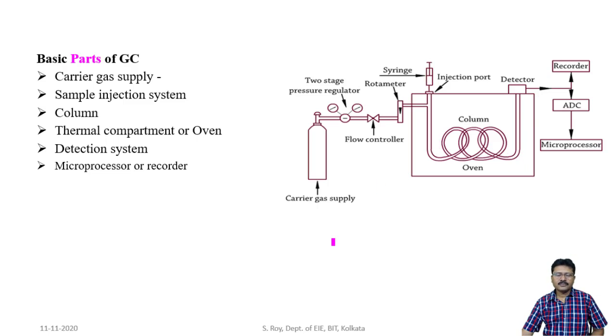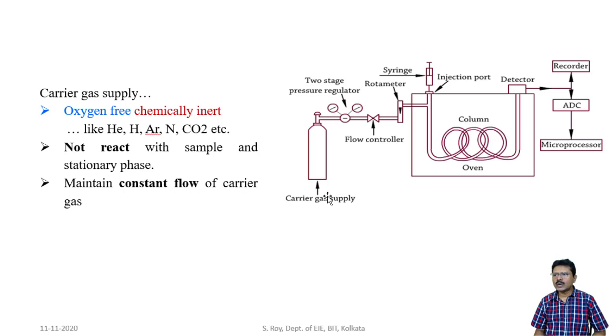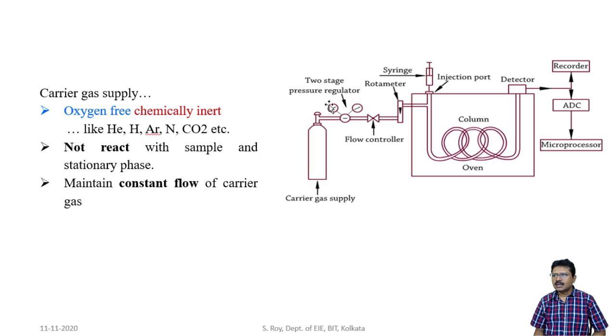The carrier gas is supplied from a source. In general, the carrier gas is helium, hydrogen, nitrogen, argon, carbon dioxide, etc. The carrier gas should not interact with the sample nor with the stationary phase. The carrier gas should maintain a constant flow; to maintain that constant flow, a pressure regulator and flow controller are used.